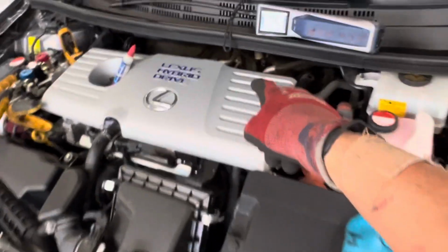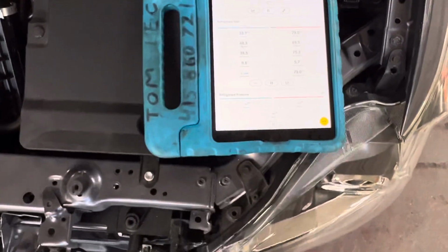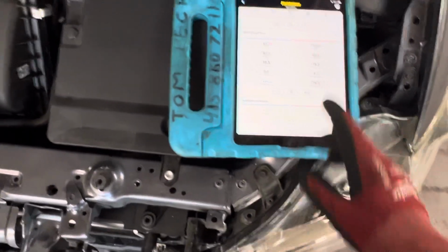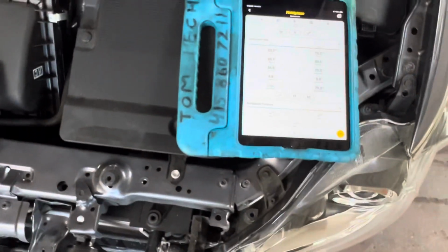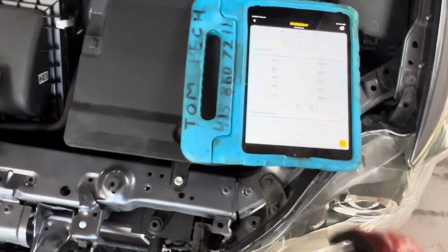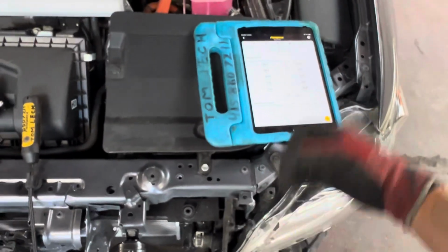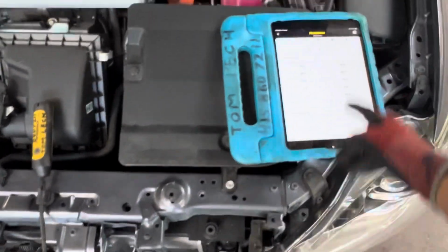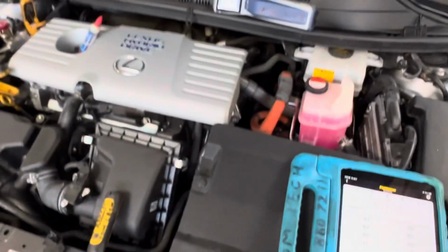It's an expansion valve system. Right there is sitting the expansion valve, but it only has a 6 subcool. It's not low. That is charged up to 470 grams, what the manufacturer requires by weight. Not guessing, squirting in cans and going by some pressure or going by dash.